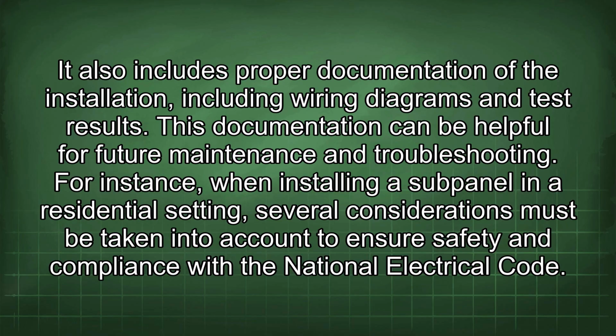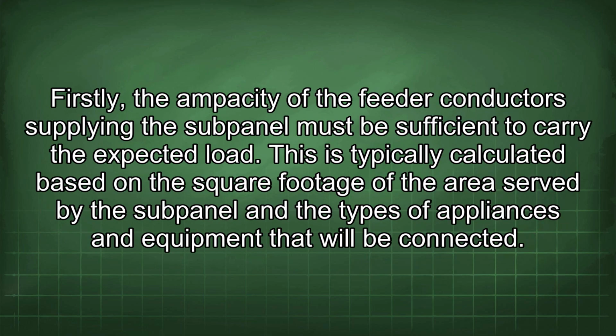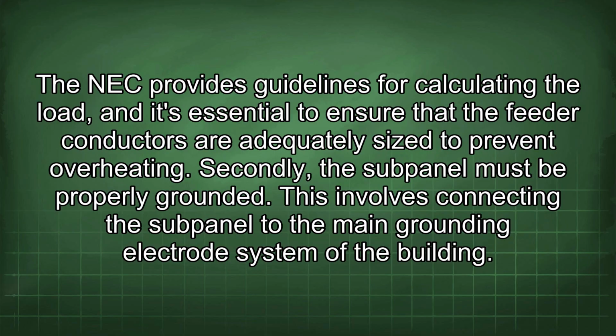For instance, when installing a subpanel in a residential setting, several considerations must be taken into account to ensure safety and compliance with the National Electrical Code. Firstly, the ampacity of the feeder conductors supplying the subpanel must be sufficient to carry the expected load. This is typically calculated based on the square footage of the area served by the subpanel and the types of appliances and equipment that will be connected. The NEC provides guidelines for calculating the load, and it's essential to ensure that the feeder conductors are adequately sized to prevent overheating.